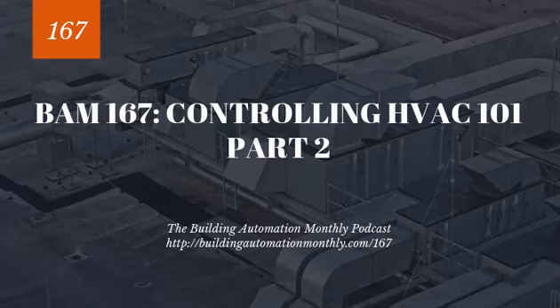Fans move air. Now, you've got primarily two types of fans. Variable speed fans, where you're typically varying the speed or frequency of the fan and driving towards a static pressure setpoint. So static pressure is typically 2/3 down the longest run, although I don't really like that rule of thumb.